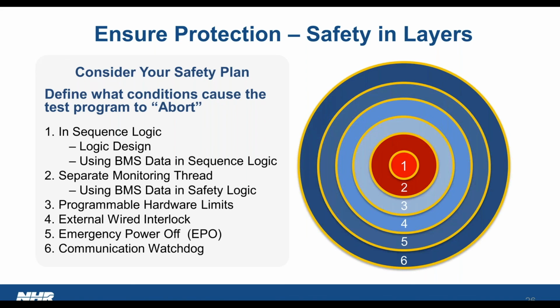We then wrap those programming layers with hardware layers, such as hardware limits acting like programmable fuses, external interlocks and EPOs allowing an external device to shut the hardware down if it monitors something, and of course the communications watchdog. If there's any communications loss, that overrides everything else and shuts down the system as well.